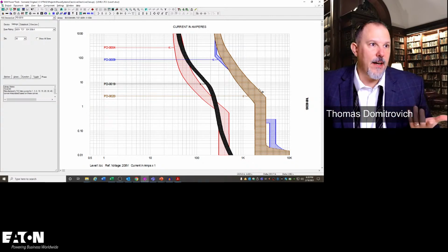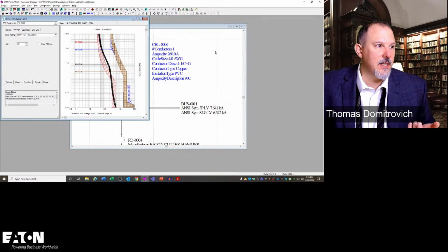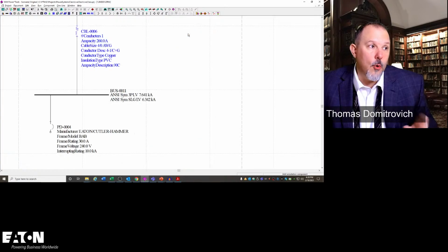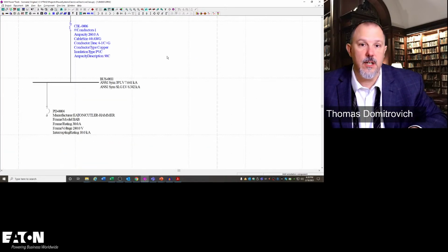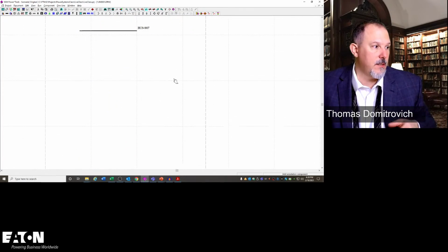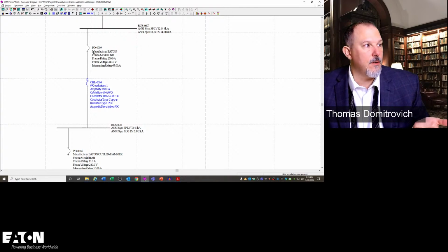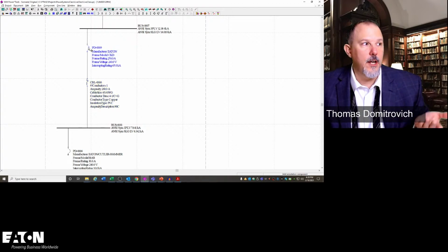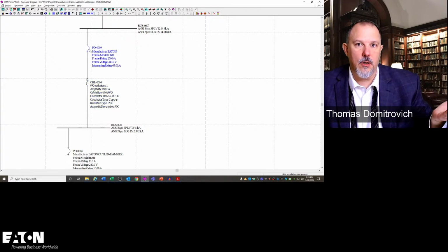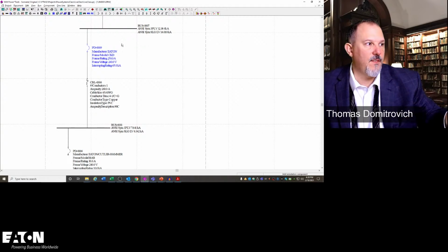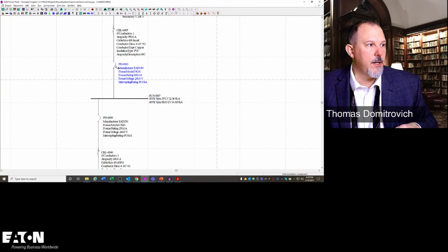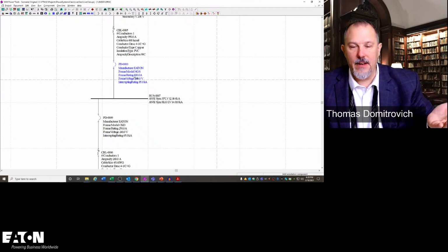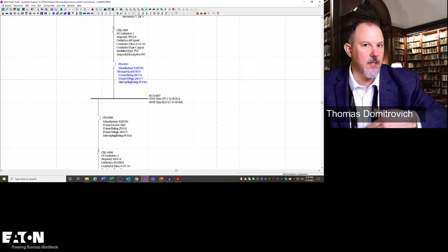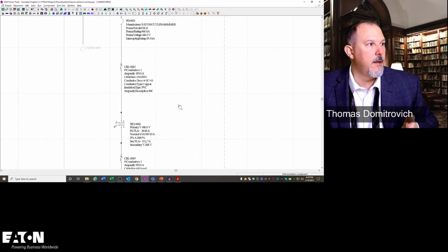Now, if I was going to look at this system and selectively coordinate it using all fuses, it's very simple. I have a 30 amp fuse here. I use a class J fuse. So as long as this is 60 amps or larger, I selectively coordinate up to 200,000 amps. I could put a 250 amp fuse there, be done. This overcurrent device just needs to be 500 amps or more. I have it as an 800 amp, so an 800 amp fuse selectively coordinates up to 200,000 amps.